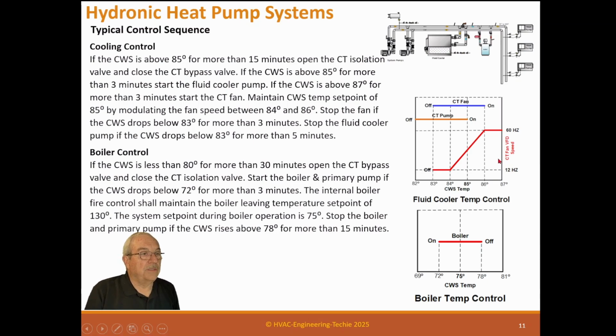Boiler control. If the condenser water supply is less than 80 degrees for more than 30 minutes, open the cooling tower bypass valve and close the cooling tower isolation valve. Start the boiler and primary pump if the condenser water drops below 72 for more than 3 minutes. The internal boiler fire control shall maintain the boiler leaving temperature set point of 130 degrees. The system set point during boiler operation is 75 degrees. Stop the boiler and primary pump if the condenser water temperature rises above 78 degrees for more than 15 minutes.